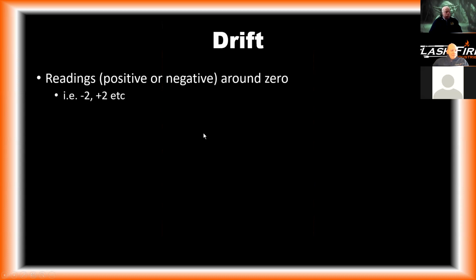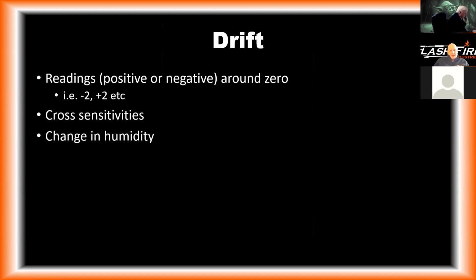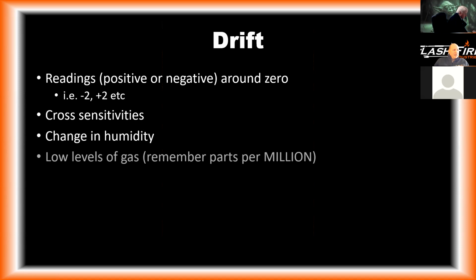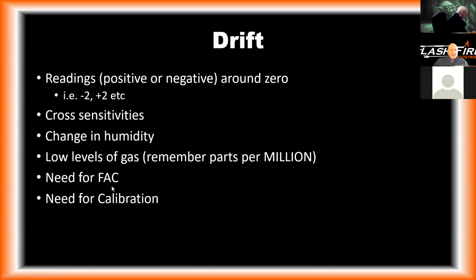All right, drift. I mentioned this a little bit, positive or negative readings around 0. This could be because of cross sensitivities. It could be because of change in humidity. If you fresh air cal'd the meter on a day that had 10% humidity, and now today's a 90% day of humidity, that could definitely cause that little bit of drift. It could be low levels of gas. It could be the need for a fresh air cal. It could be the need for a cal. If we haven't calibrated the meter in a while, we will start to get some drift.